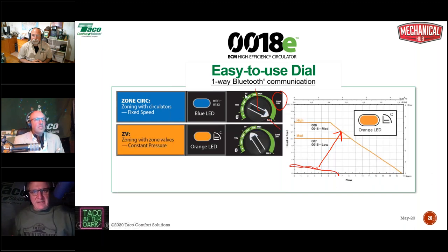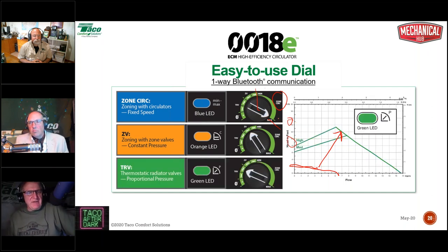All righty. The next operating mode we have is zone valve. These are constant pressure modes. There's two constant pressure settings, medium and high, at 10 foot head and at 15 foot head. All right, two constant pressure settings, and it says ZV there for zone valves. And then lastly, you have TRV, thermostatic radiator valves.